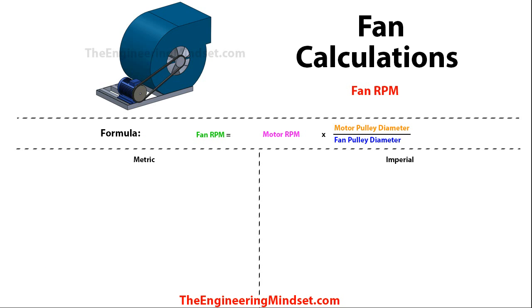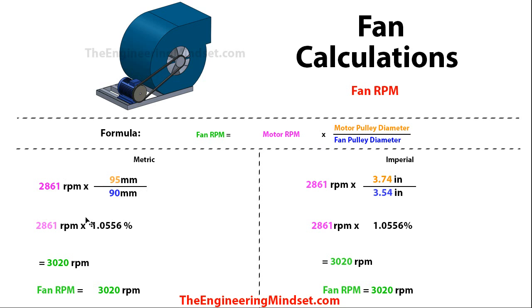So then we can look at what the fan RPM needs to be in order to achieve our design criteria. The formula is: the fan RPM is equal to the motor RPM multiplied by the motor pulley diameter divided by the fan pulley diameter. We should have calculated or taken these figures from the manufacturer. Dropping the numbers in gives us a ratio from the division of the pulley diameters, and multiplying these together brings us to 3,020 RPM on both metric and imperial — that is the speed the fan needs to rotate at to achieve the design flow rate.